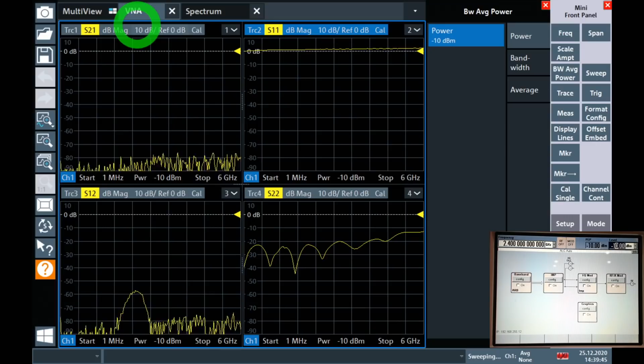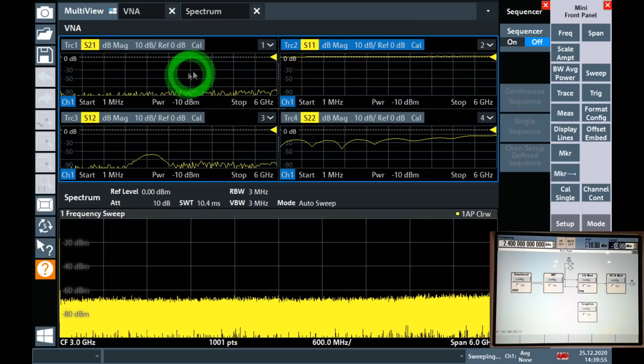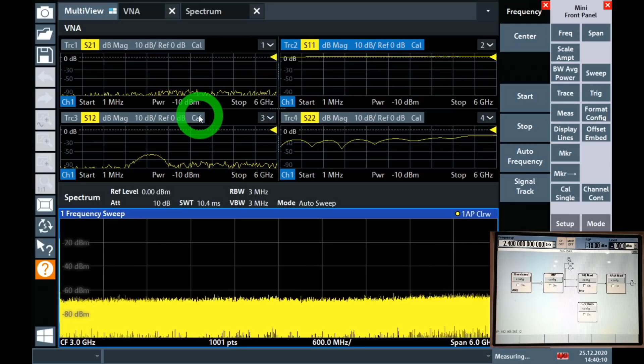This is a really powerful feature. This is one of those things that Rohde & Schwarz pioneered and had across several of their instruments, allowing you to have multiple tabs with different settings active at the same time and just quickly jump between them. If you go into the multi-view, you can even get all of them at the same time, and whichever one is selected is getting updated. So if I select the spectrum analyzer, the spectrum analyzer begins to update. And you can even adjust this such that it does them sequentially. So it performs a VNA, then it jumps to the frequency sweep, and it jumps to something else if you have multiple tabs. This is really great and perfect for an instrument like the ZNL that has many different functions at the same time.